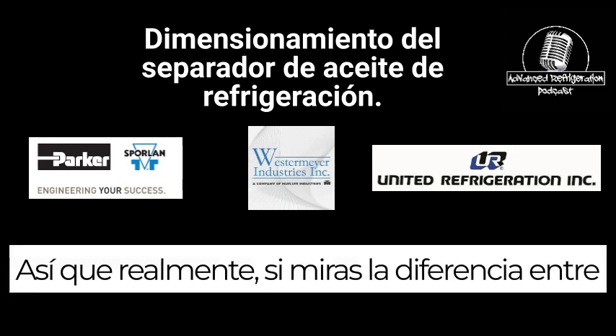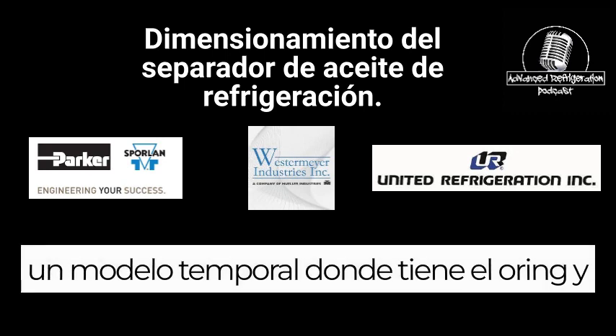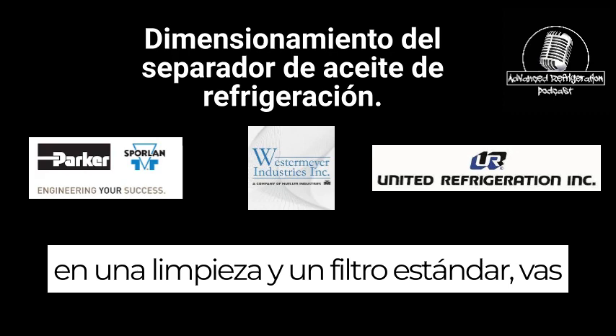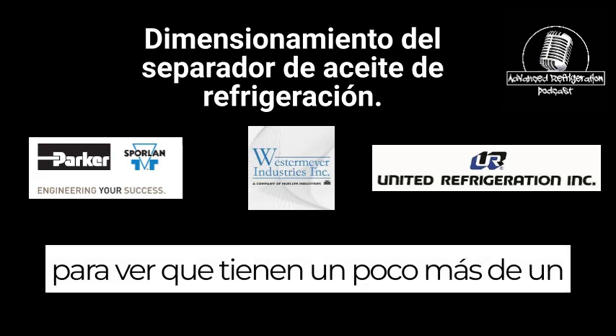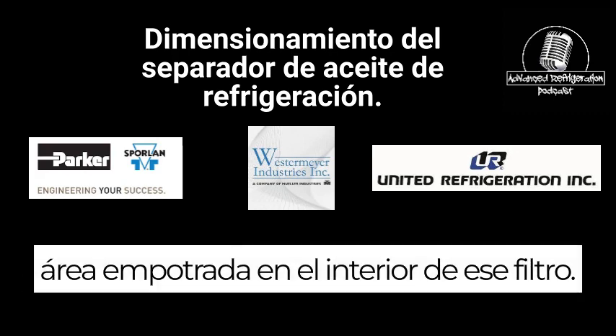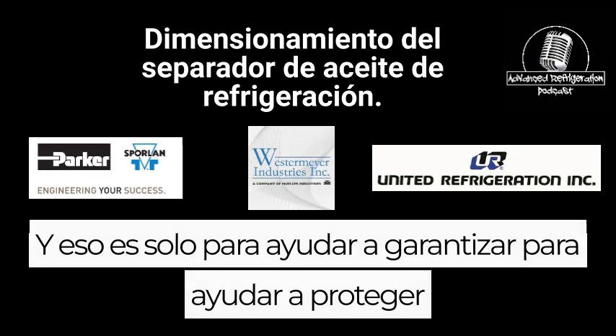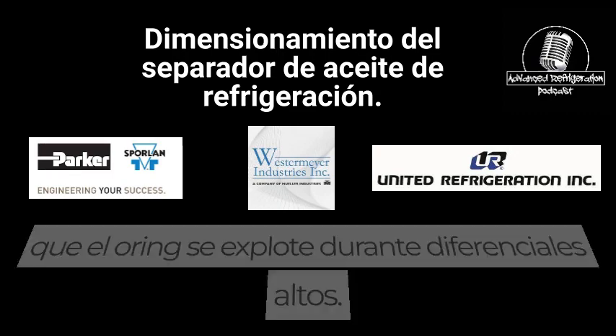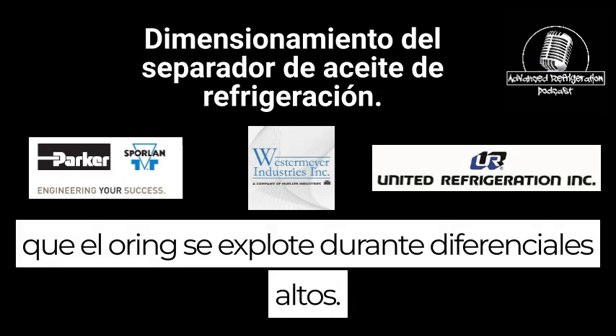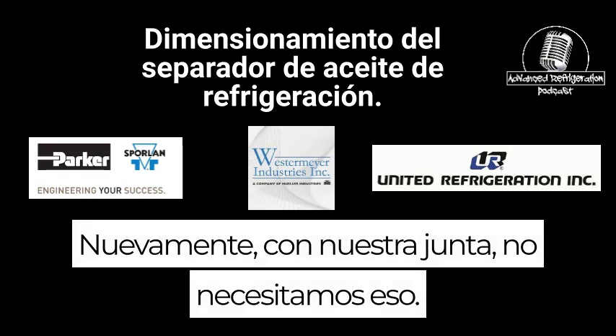So really, if you look at the difference between a Temprite model where it has the O-ring and a cleanup and a standard filter, you're going to see they have a little more of a recessed area on the inside of that filter. And that's just to help protect that O-ring from blowing out during high differentials. Again, with our gasket, we don't need that.